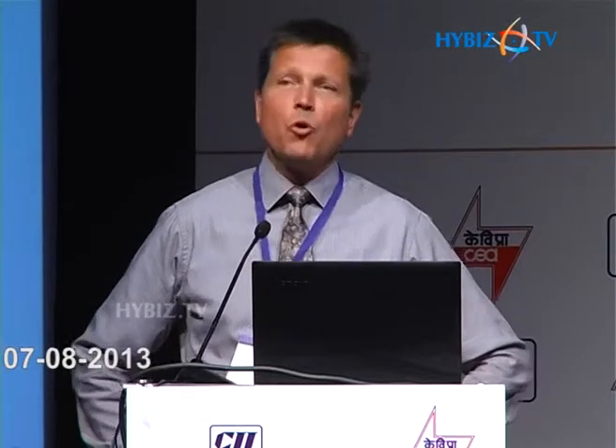Why do you use emission monitoring at all? Well, of course, you have environmental regulations, and they're getting more and more stringent year after year. We have a number of regulations in Europe, for instance, that we have to meet. And basically, all industries that have some kind of emission need to have analyzers to monitor that they are below the approved emission limits. And in the stack you have a number of gas pollutants. Normally you would look at NOx, SO2, maybe CO, CO2, and so on. But with our system you can monitor hundreds of different gas pollutants.